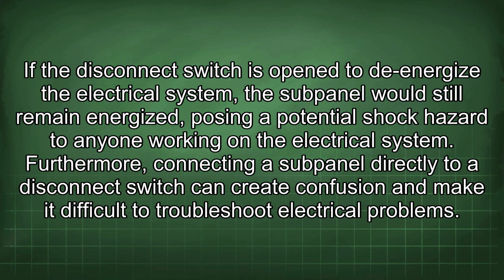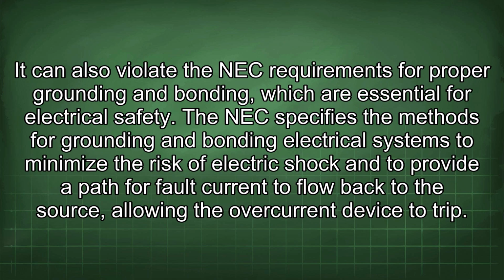Furthermore, connecting a subpanel directly to a disconnect switch can create confusion and make it difficult to troubleshoot electrical problems. It can also violate the NEC requirements for proper grounding and bonding, which are essential for electrical safety. The NEC specifies the methods for grounding and bonding electrical systems to minimize the risk of electric shock and to provide a path for fault current to flow back to the source, allowing the overcurrent device to trip.